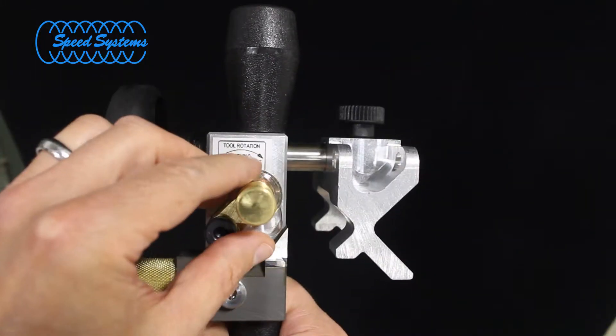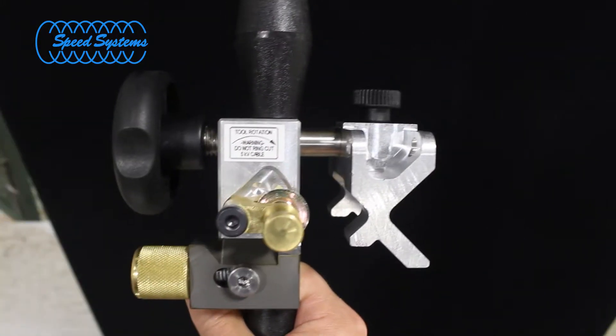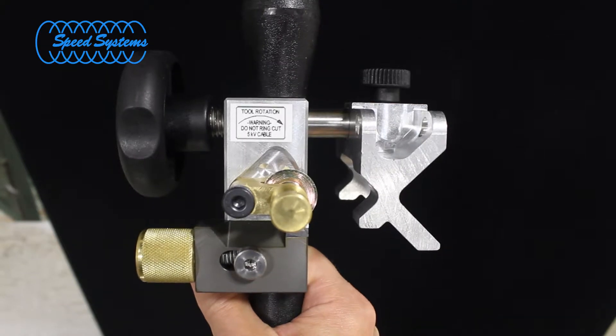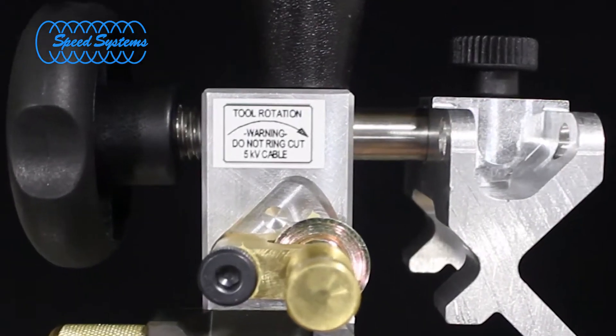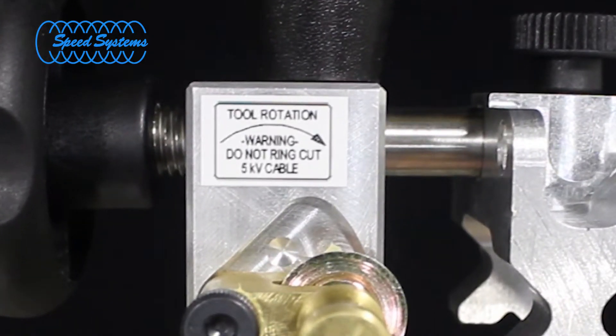Move the ringing blade to the down position when mid-span stripping 15kV through 35kV cable. Do not engage the ringing blade on 5kV cable.